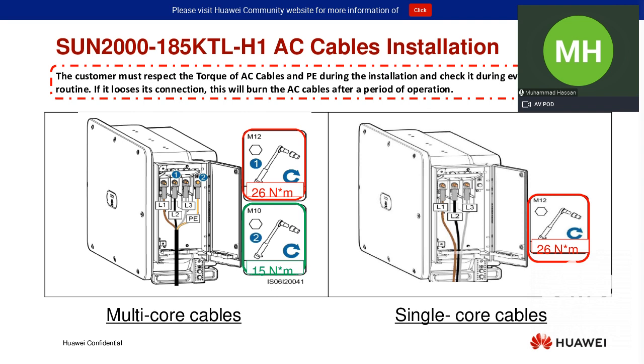As I explained before, always focus on the torque settings on the AC terminals. If you are using multi-core cables, you need to apply 26 Newton meter torque on L1, L2, and L3, and 15 Newton meter torque on the PE connection. And if you are using single core cables, the 26 Newton meter torque applies to the AC connectors for that inverter. So always apply the proper torque settings.